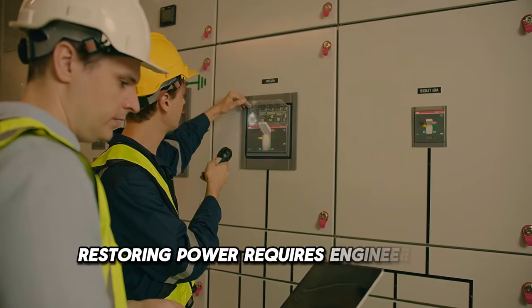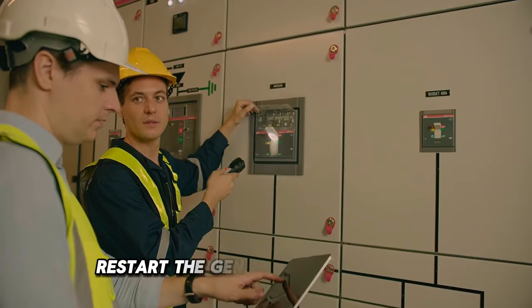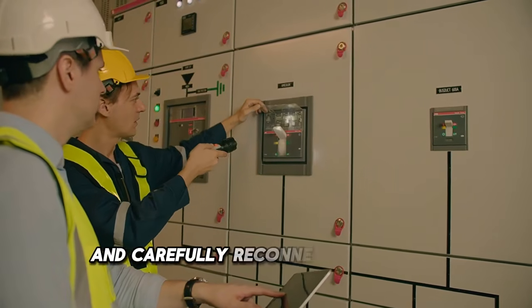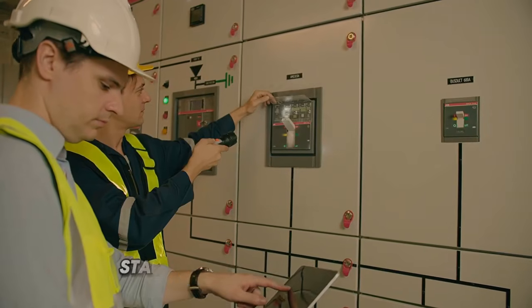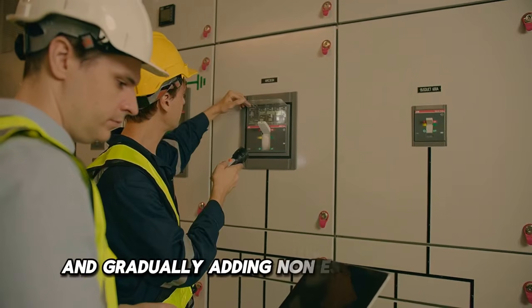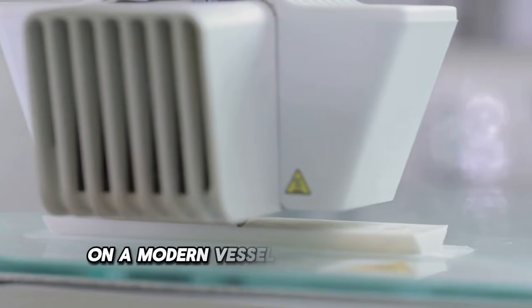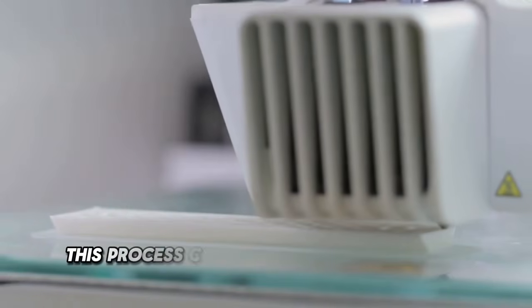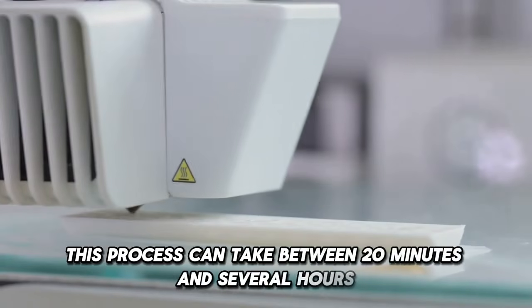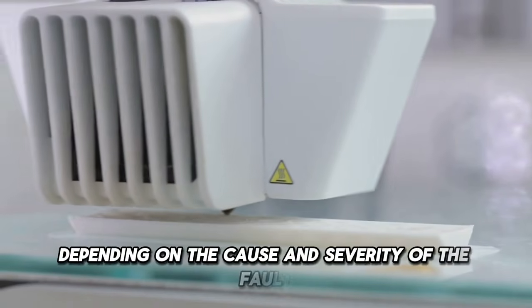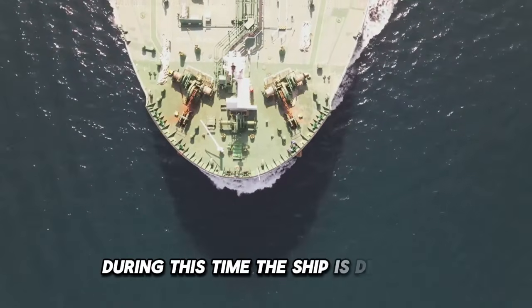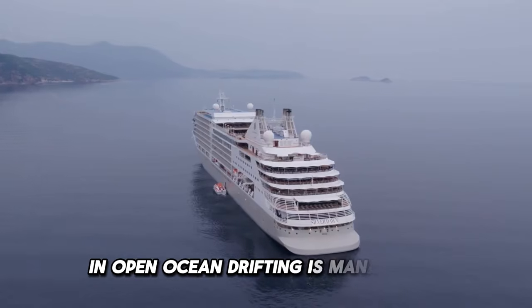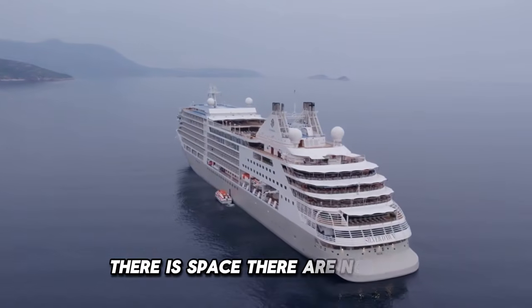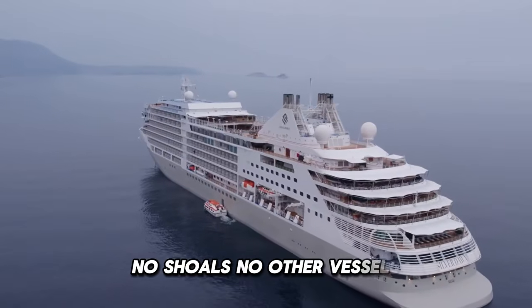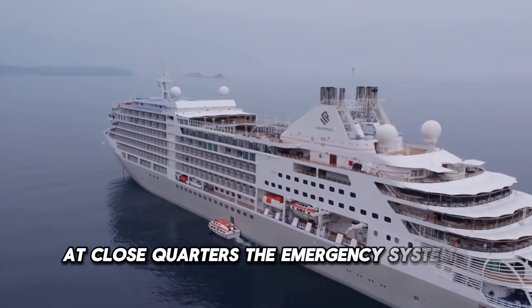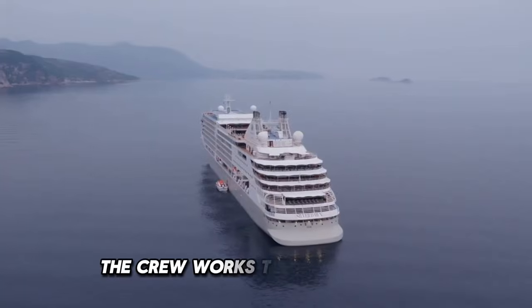Restoring power requires engineers to isolate the fault, restart the generators in sequence, and carefully reconnect loads in a controlled order, starting with critical systems and gradually adding non-essential loads. On a modern vessel with experienced engineers, this process can take between 20 minutes and several hours, depending on the cause and severity of the fault. During this time, the ship is drifting. In open ocean, drifting is manageable. There is space. There are no reefs, no shoals, no other vessels at close quarters. The emergency systems keep people safe. The crew works to restore power.